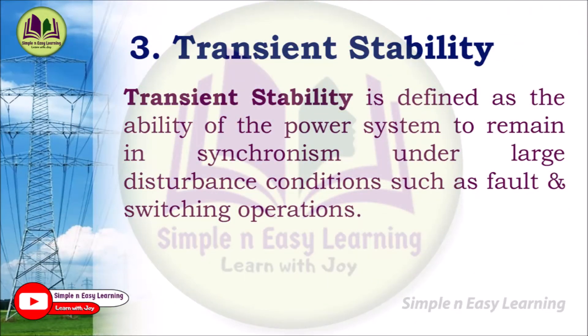The third analysis is transient stability. Transient stability is defined as the ability of the power system to remain in synchronism under large disturbance conditions such as faults or switching operations. When a sudden fault occurs, there will be oscillations and voltage fluctuations in the system — this is called a disturbance. In some cases, switching operations such as sudden inclusion or removal of load will also lead to a disturbance to the overall system, and the stability gets disturbed.